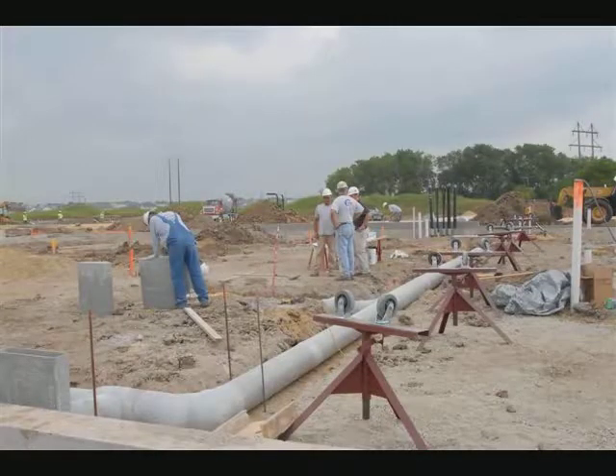At Crawford we made those tripod stands, putting casters upside down on top of some C-channel so you could set the 20-foot lengths on top. Made it very easy to roll around, especially when doing the joints and grinding. We tried to prefab as much above ground as possible, eliminating as many joints down in the trenches as we could. We had a telehandler on site, so we were able to join 40-foot lengths from two 20-foot lengths together, taking precaution on how we raised and set them after the joints were made up.